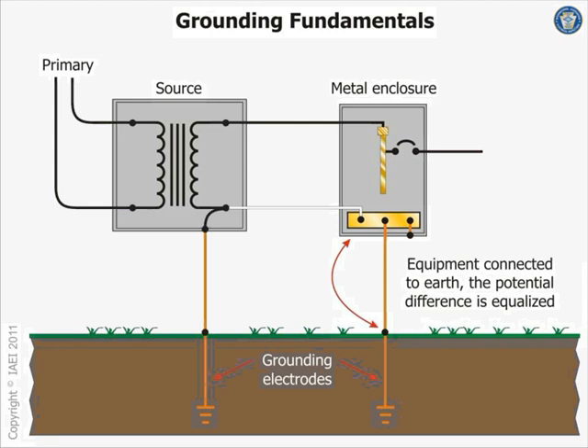Here's my system, owned and operated by the utility. They ground the reference to the ground. Here's my system, owned and operated by me. I ground my enclosures, and I tie my grounding system into the utility's through my what? Neutral. So the neutral is the bridge between your grounding electrode system and the utility that provides you the grounded and their grounding electrode system. You bridge them through the neutral. Does that make sense? You can see very clearly it's bridging them, tying them together. And also they're bridged through Mother Earth. There's another alternative path here, but that's the high impedance path that shall not be depended on.